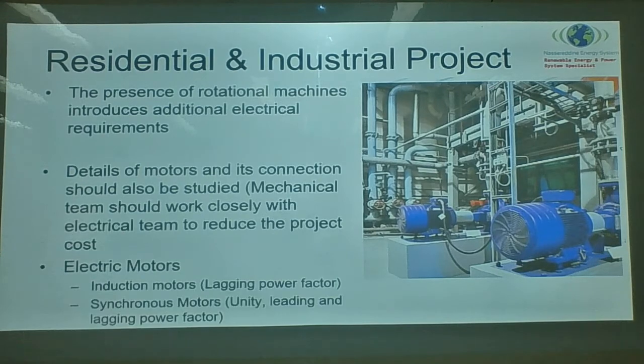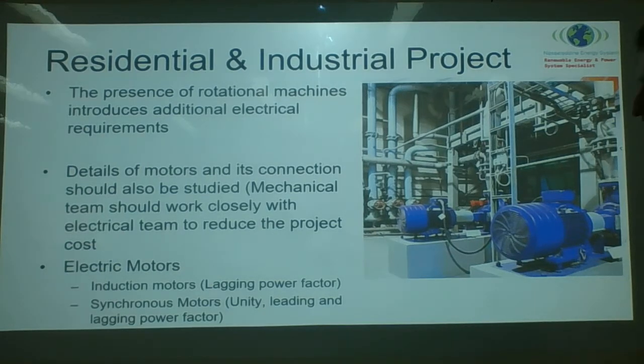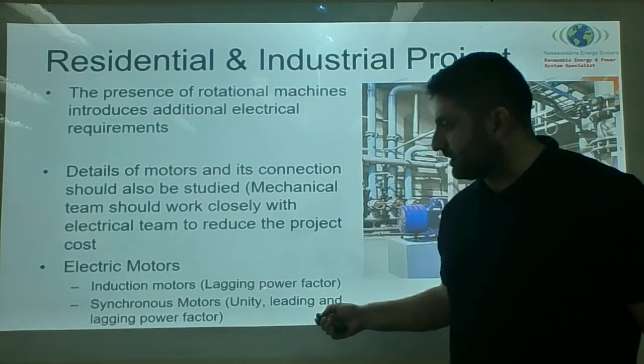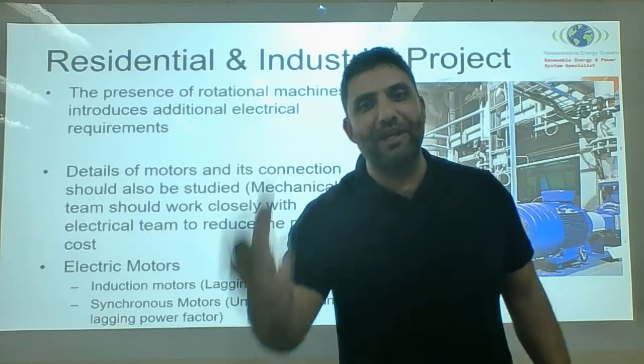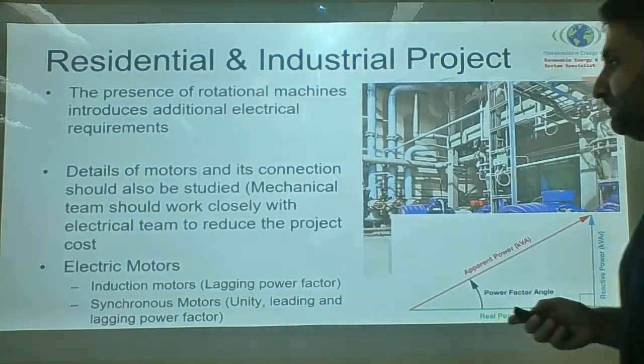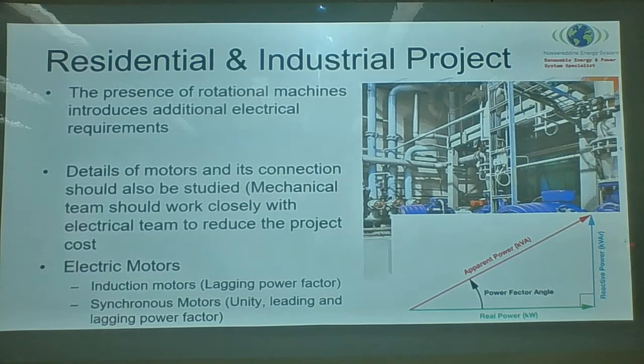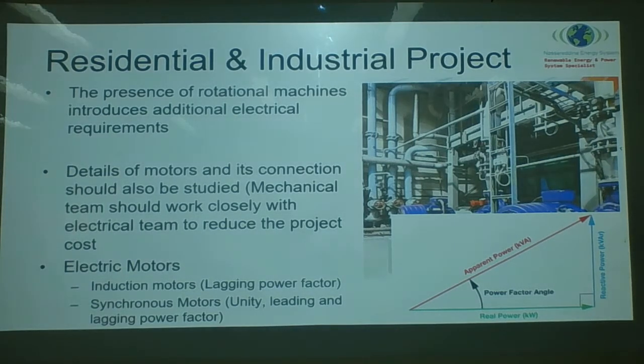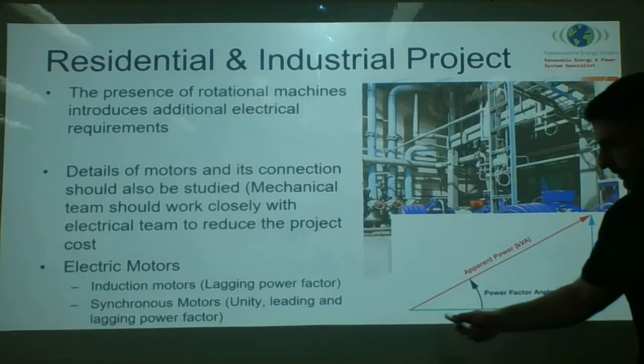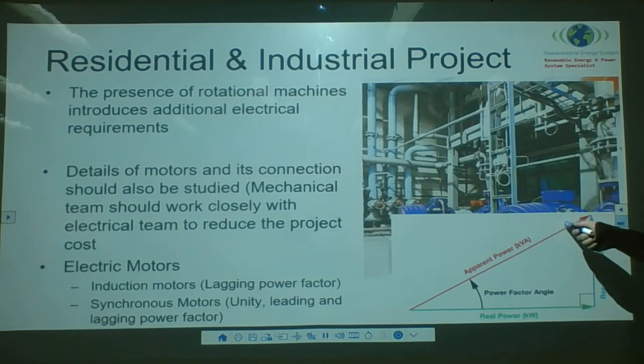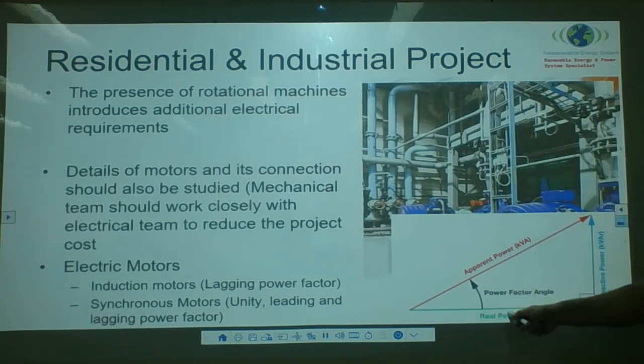Induction motors can only have a lagging power factor; synchronous motors can be designed for unity, lagging, or leading power factor. Only real power is converted into torque in the motor — so I'm drawing more current, but only the real power component represented in the current vector is converted into torque. This is why the power factor matters — to minimize excess current and improve efficiency.